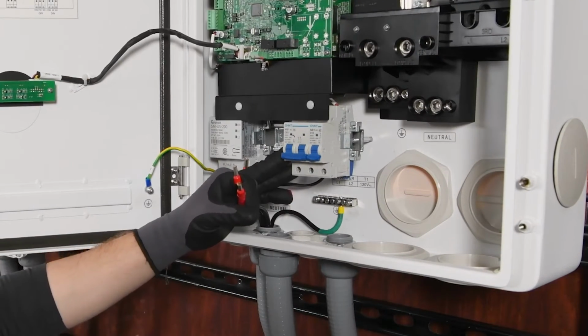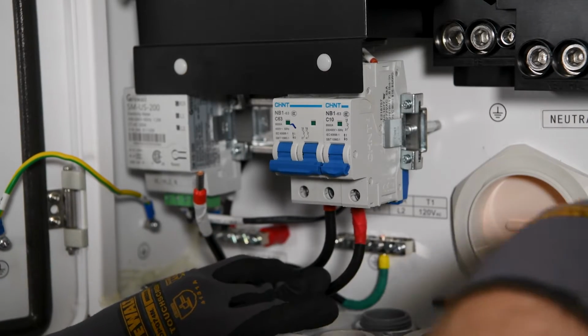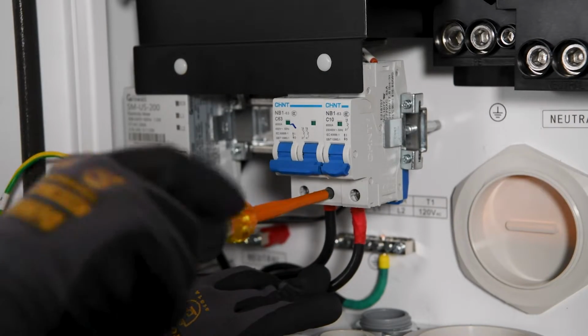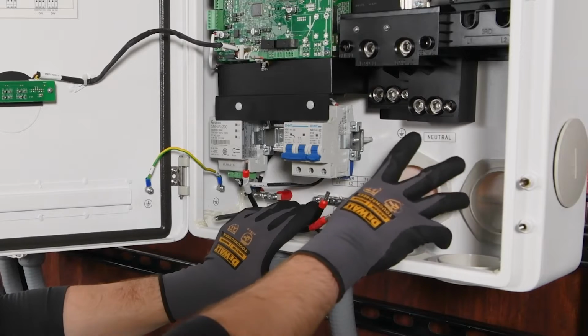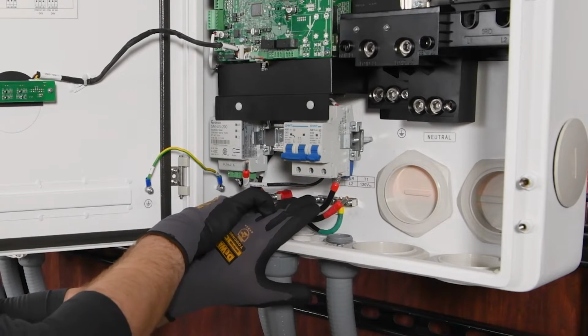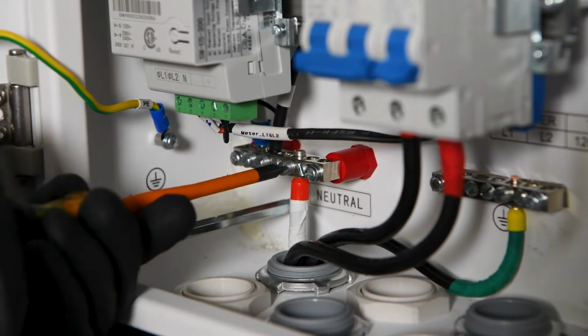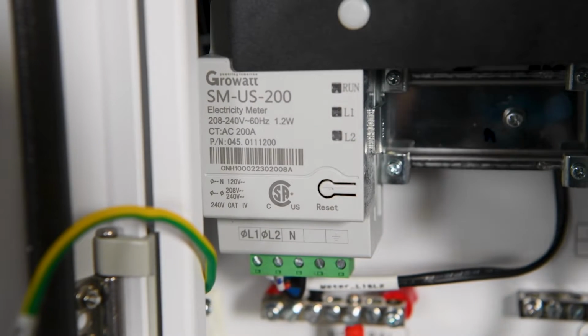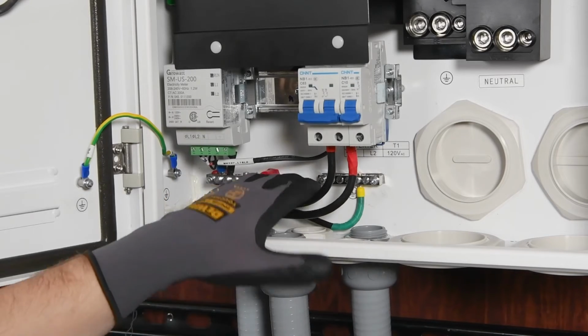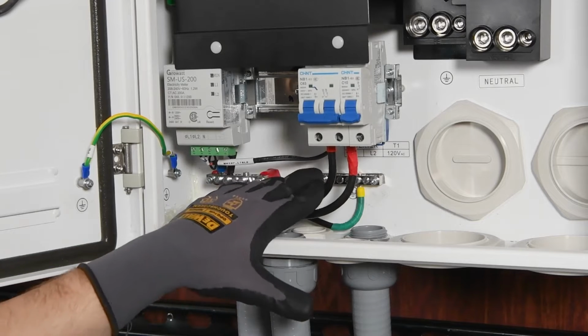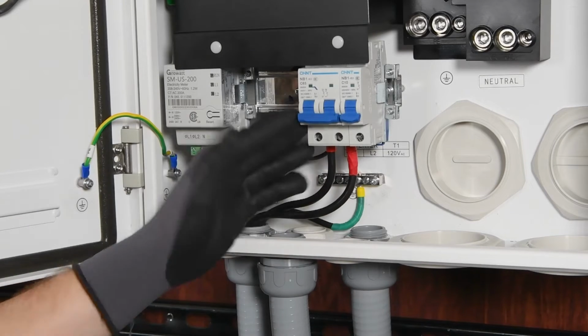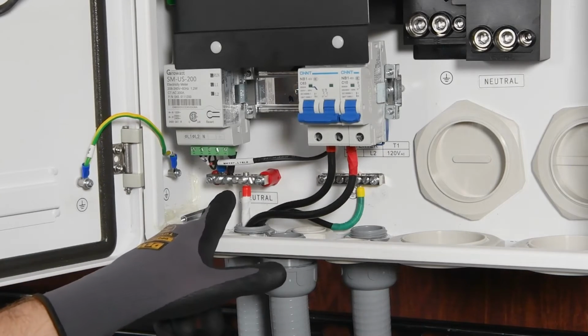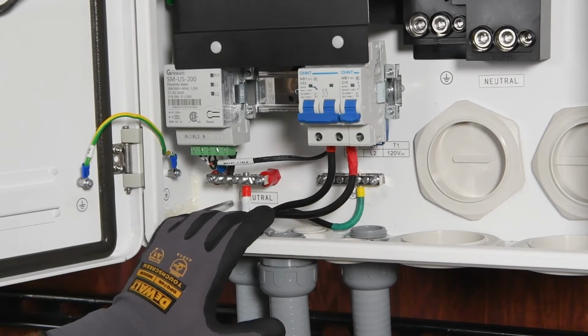This breaker right here is what we'll use to connect the output leads from our inverter. This neutral will not go to the neutral bus up here. It will actually go to a neutral bar down here, which will connect to this electricity meter. So now that we've connected all of our conductors, we have our 2 hot legs, L1 and L2, into our breaker. We have our neutral feeding to the neutral bar that will connect to this electricity meter, and our ground is connected as well.